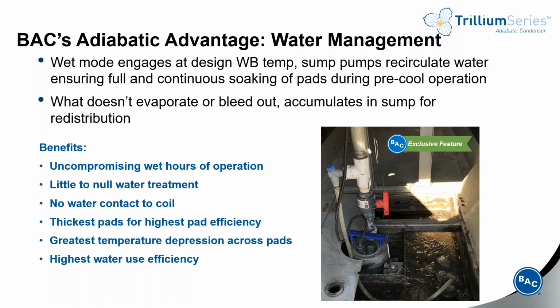The use of this water distribution system allows us to use the thickest, most efficient adiabatic media pads in the industry. If those media pads aren't being fully wetted, then we have an inefficient system and the potential for scale buildup. Using the recirculating pump and water distribution system allows us to ensure that the pads are fully wetted for more hours of operation, which allows for the maximum temperature depression across the pads, enabling the lowest condensing temperatures possible.